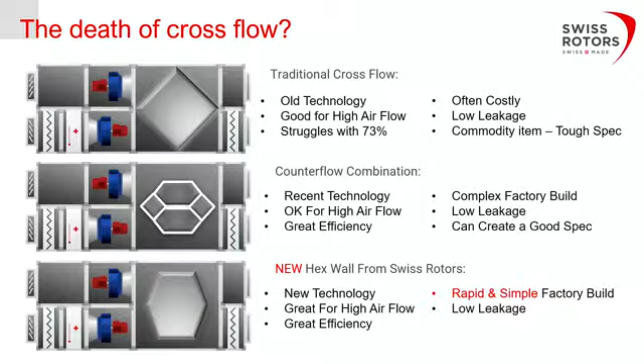These are very good for high airflow. So with this type of unit, it's not impossible to get up to 27,000 meters cubed an hour out of one of these units as it stands right now. But they're also modular, which we'll cover a little bit later. Very low leakage thanks to the sonic welding of the high efficiency composite plate heat exchanger, and they have a very high efficiency. Typically on the model that you see in front of us, you wouldn't see anything less than about 78% efficiency. That creates an unbeatable specification on size versus price versus efficiency.